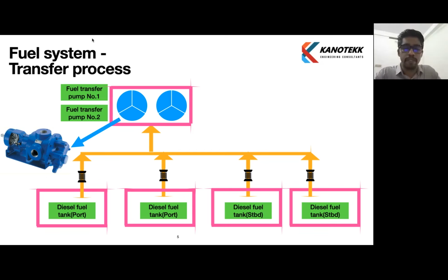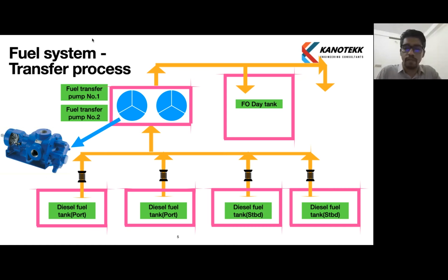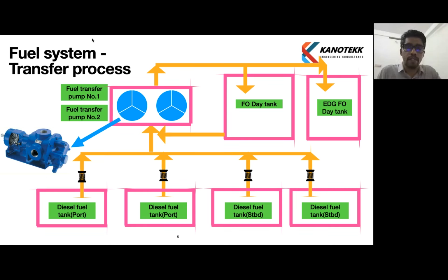These pumps take suction from the storage tanks and supply to the fuel oil day tank and the emergency generator fuel oil day tank. Sufficient isolation valves will be there. There is also an option to pump to the bunkering stations. In case we want to empty the storage tanks in an offshore oil rig, we can use the transfer pumps to pump the fuel oil stored in the tanks back to the bunkering stations, which will be connected to a supply vessel.